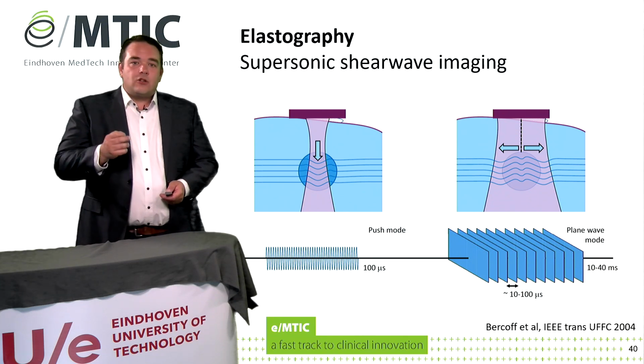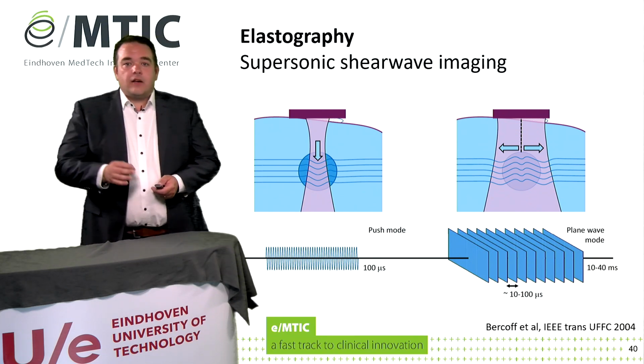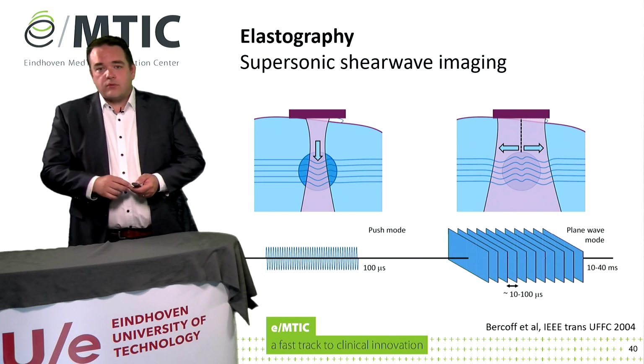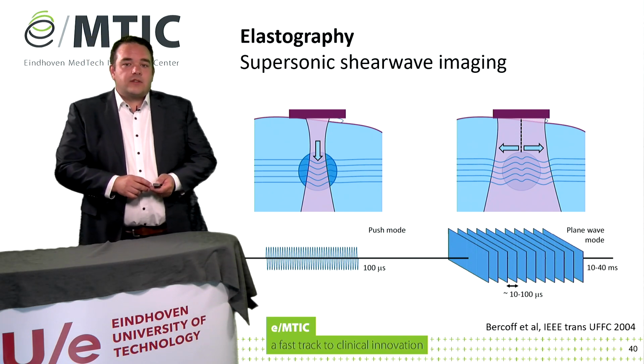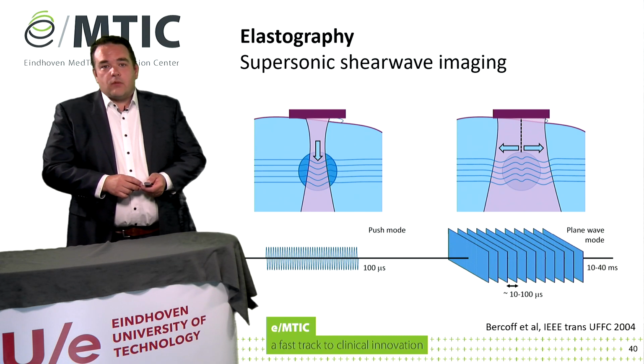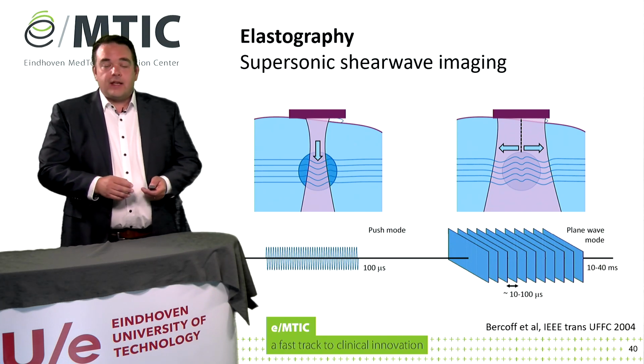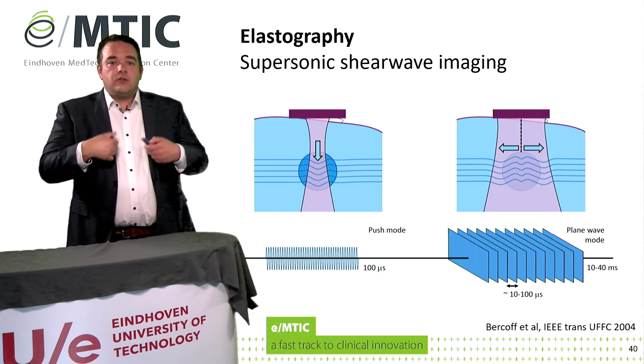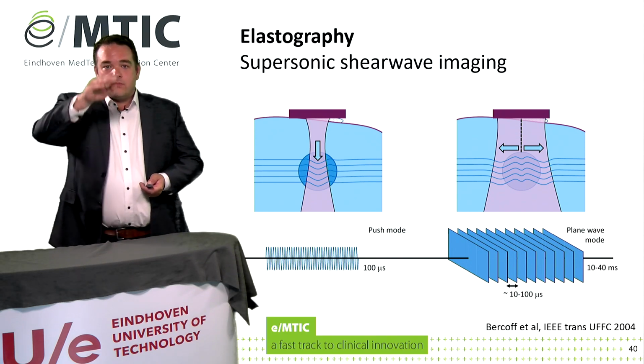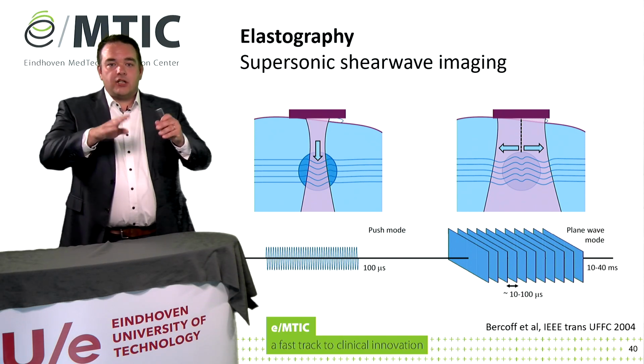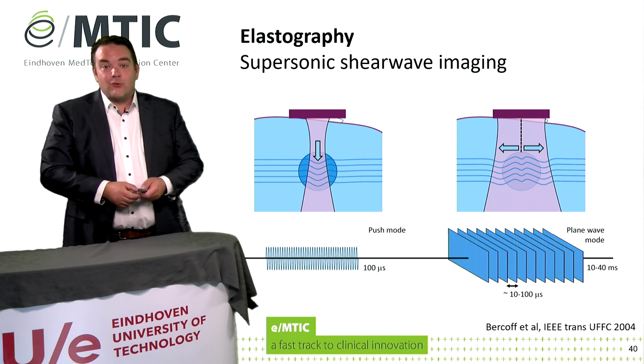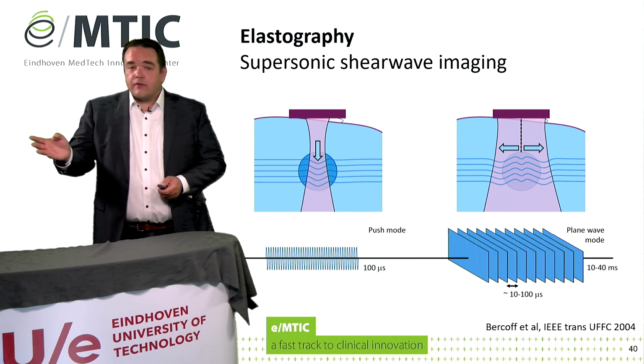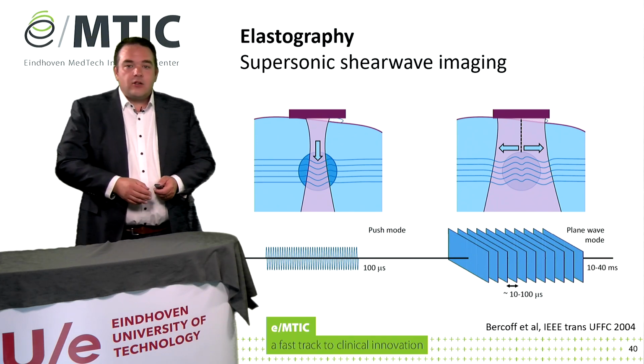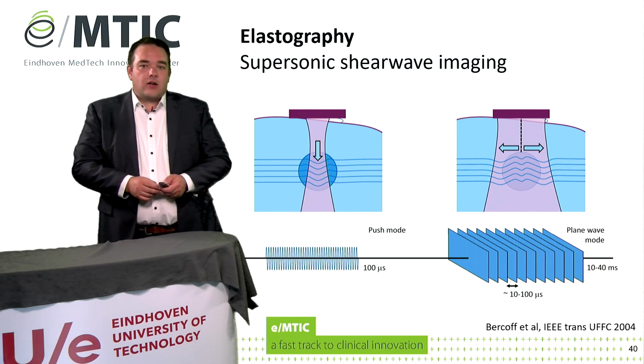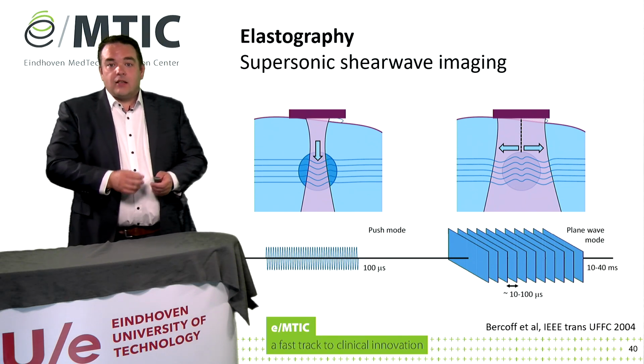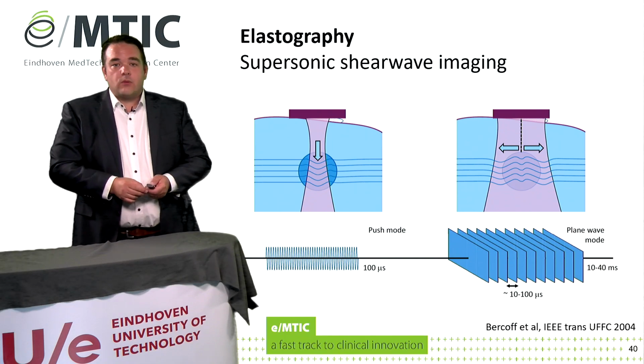If you want to do quantitative elastography, a very nice technique, and I guess also a breakthrough technique, was developed in the early 2000s by Bercoff et al., called supersonic shear wave imaging. There you focus the ultrasound, create an acoustic radiation force, and push the tissue, and as a result a shear wave propagates in the transverse direction. With the ultra-fast imaging that Massimo just discussed, we can image the tissue at such a high frame rate that we can follow this shear wave through the tissue.